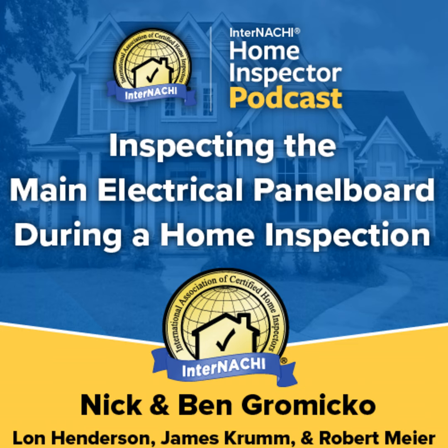Many inspectors, contractors, and electricians refer to the panel board and cabinet together as the panel, breaker box, or breaker panel, and they do not necessarily distinguish between the cabinet and the panel board. For simplicity, home inspectors could use the term panel board to refer to the cabinet and panel board as a unit. Working space and clearance.